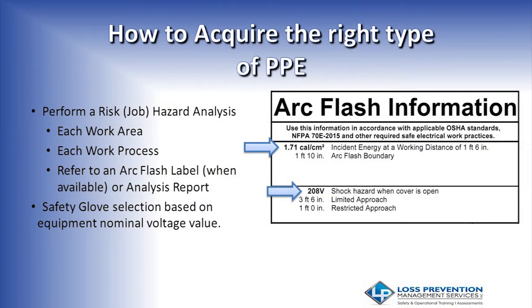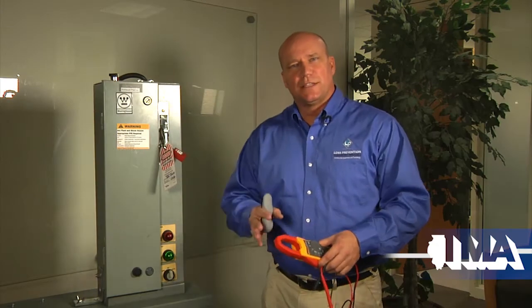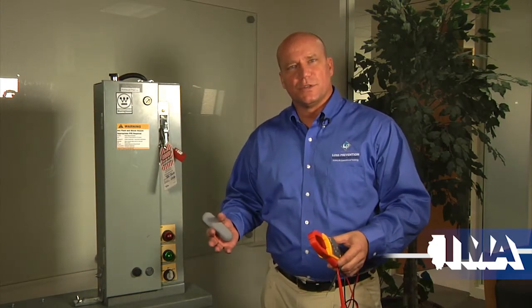On the slide is a typical arc flash label. It might be different from one engineering firm to another as far as formatting, but the general locations of this information are pretty much similar from one location to another. If you look at the label, the arc flash boundary is set at the onset of second degree burns. It will vary based on the incident energy. In this case, at the work zone, it was 1.7 cal per centimeter squared. And then beyond that, or inside that, was the arc flash boundary.